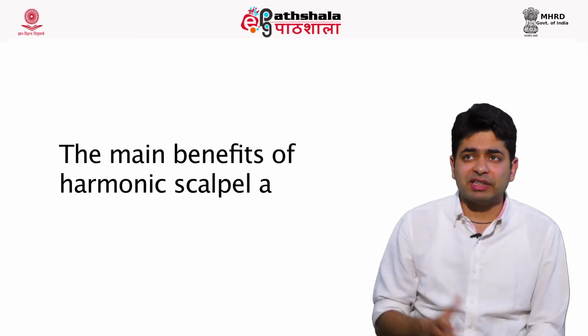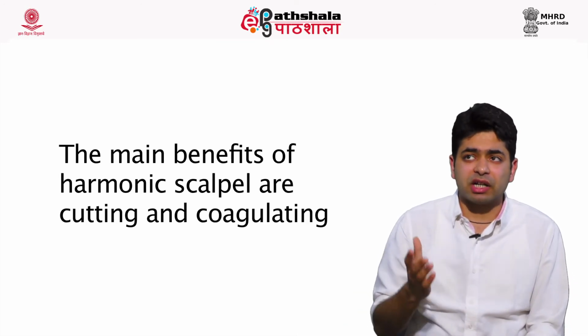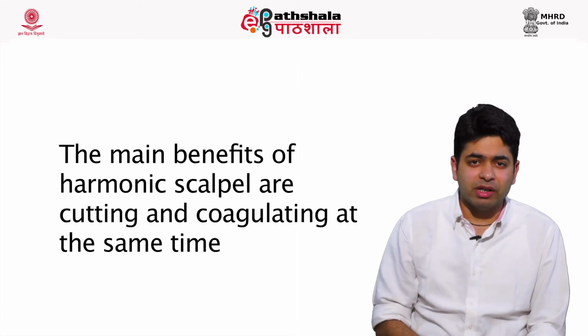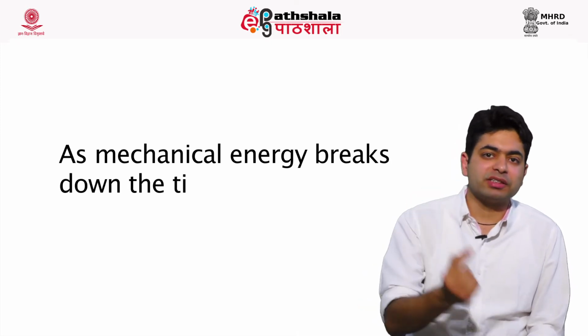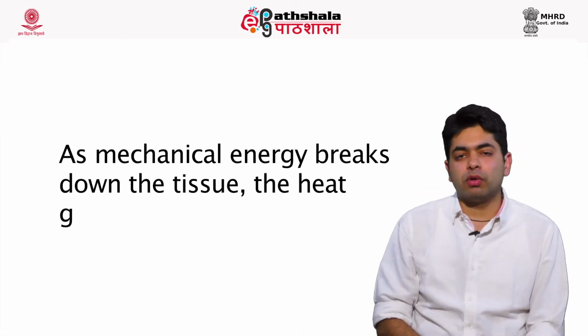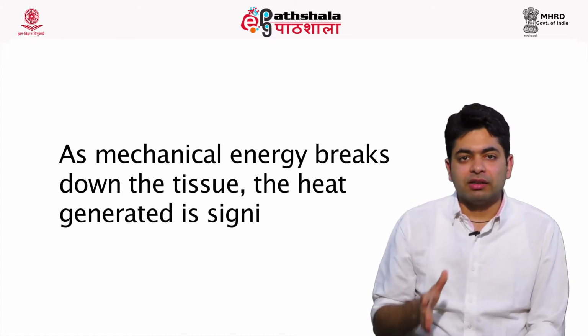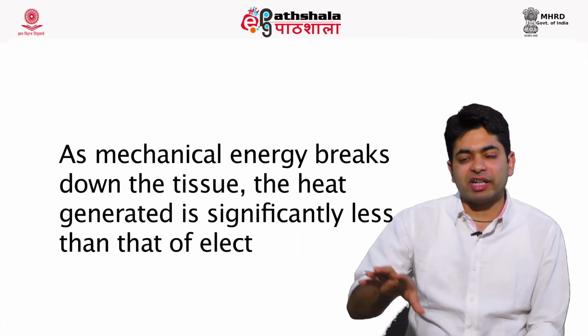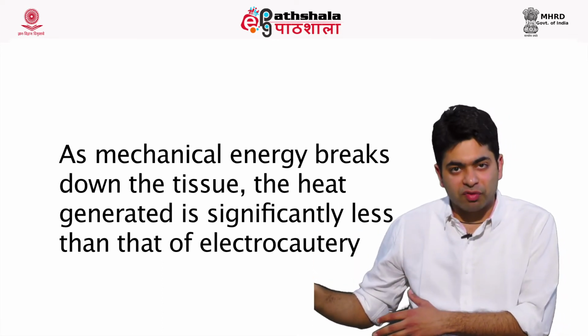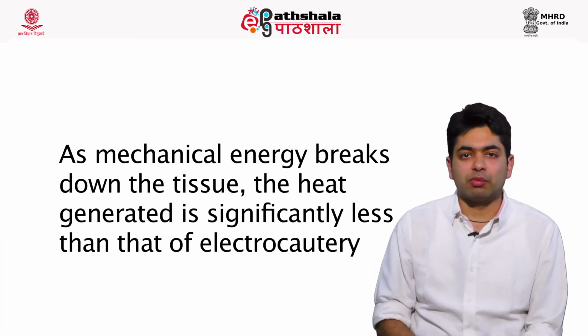The second, again discussing the main benefit that I have already mentioned in this slide, is cutting and coagulating takes place at the same time. Another benefit is that it is using mechanical energy. The electrical energy itself is not passing through the tissue. So the problems of monopolar cautery, that of lateral thermal spread or electrical energy spread that were affecting the other implants in the body of a patient, are not there with harmonic scalpels.